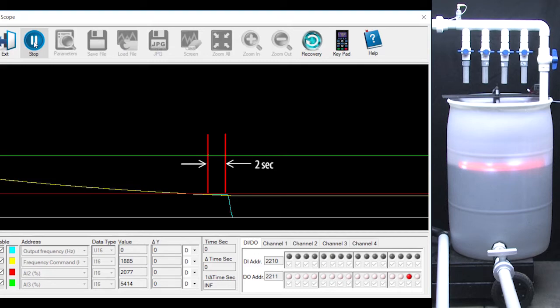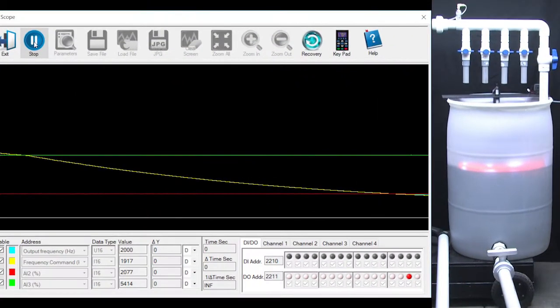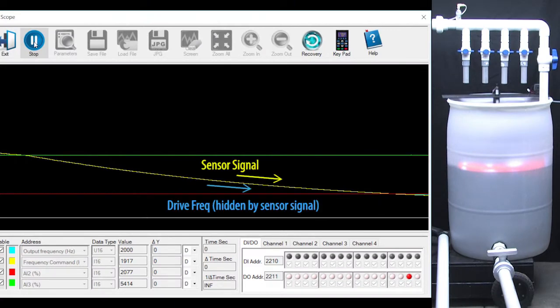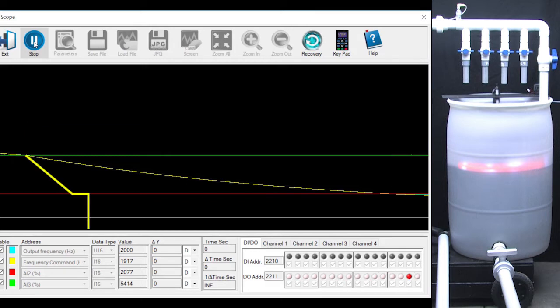This looks ok, but there are two big problems with this. First, since the sensor returns smaller and smaller values as the tank fills, the drive frequency will get smaller and smaller and the motor will turn slower and slower. All of which means it will take a long time to fill the tank. Wouldn't it be better if the motor could just quickly fill the tank at full speed all the way up and save this time?